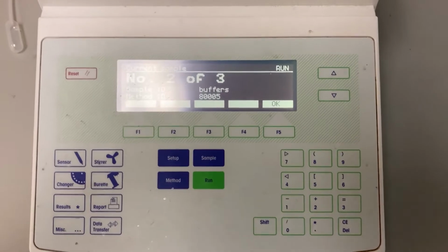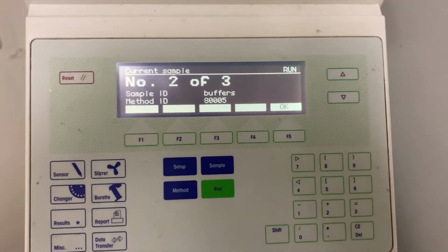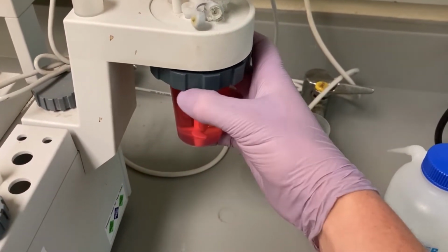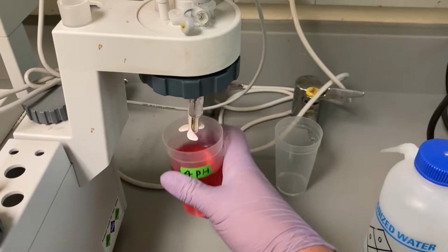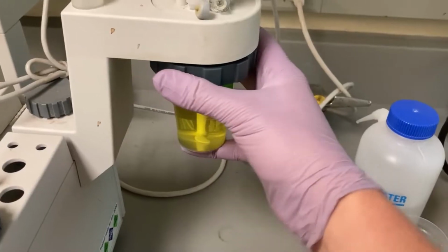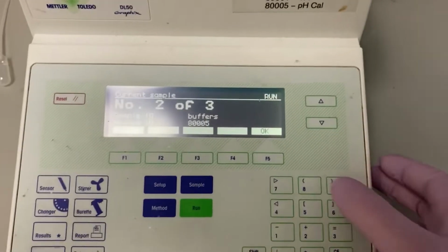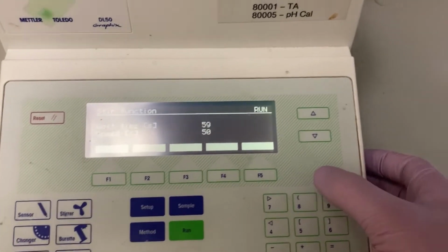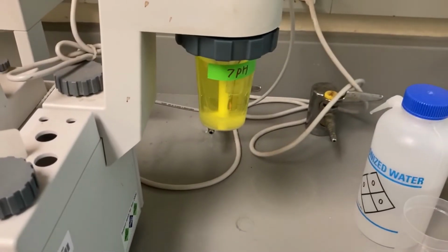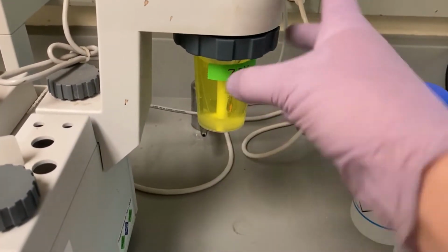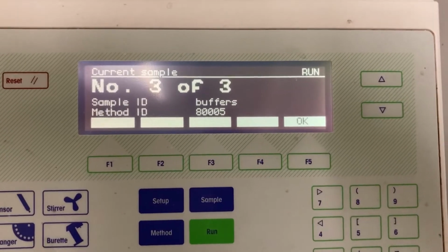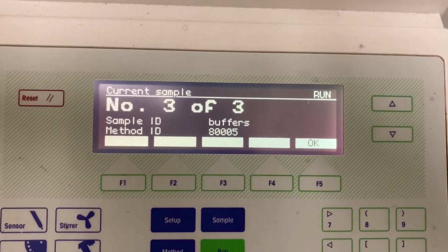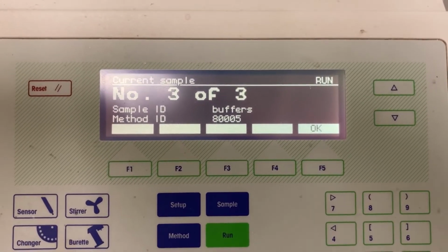All right, when it's done with the 4 pH buffer, it will say number 2 of 3. So you'll know it's done. So we can just take 4 off. Make sure to wash it. So you just put the 7 in, hit OK, and then it will start. Okay, if you hear that, it's just the propeller colliding with the cup. You can just adjust it until it's no longer colliding. Okay, after 1 minute, you'll see this menu, and then you can swap out the 7 for the 10.